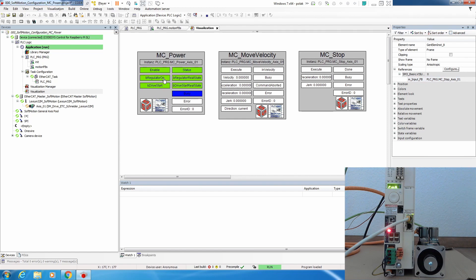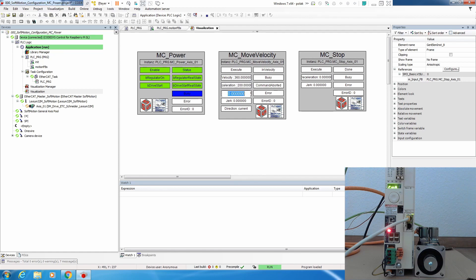Okay communication is running, we enable our drive, it's in run and now we set up velocity. So now if we put 360 this would mean we want 360 degrees per second. Let's put some acceleration 200, 200 the acceleration, this is minimum that is needed for this function block and let's execute.